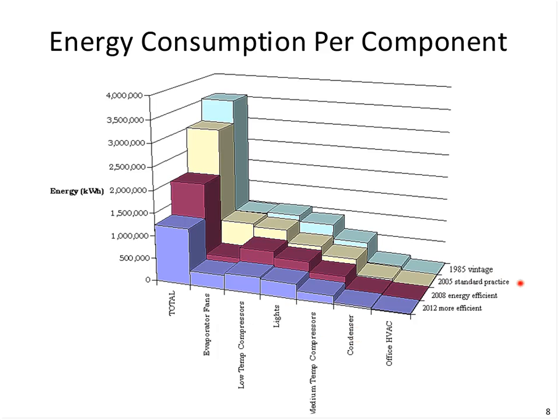Typical standard practice in 2005. Many of the efficiency measures that we're going to cover today were not considered standard practice at that time, not necessarily. Let's look at 2008 energy efficient. So let's have more efficient refrigeration, increase insulation around the building, variable frequency drives on the evaporator fans, floating head pressure, variable speed drives on the condensers, and we can see the significant reduction in energy use here.